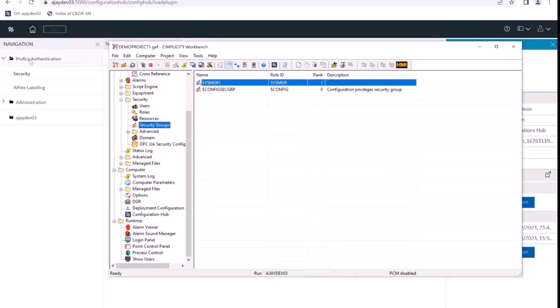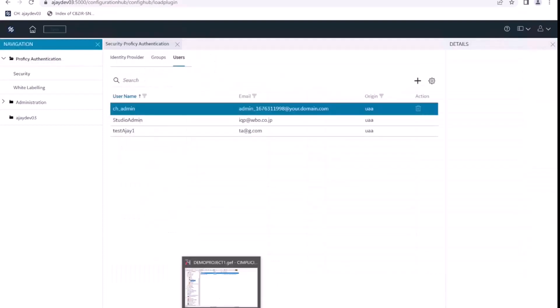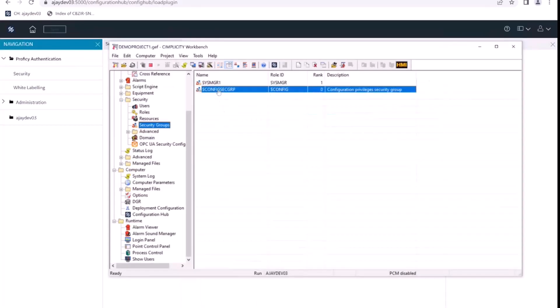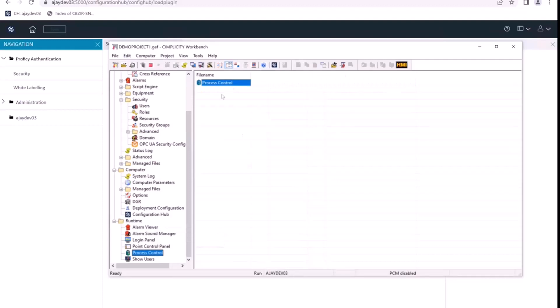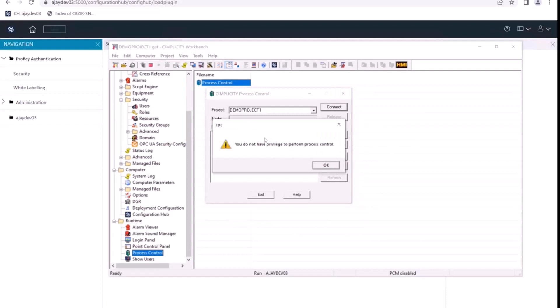Looking at Configuration Hub, we know that ch_admin has both scopes: the node-level scope, which is config sec group, and we have also assigned sysmgr1 to that user. So what rank would have priority? We gave rank one to sysmgr1, meaning that when we log in to CIMPLICITY, ch_admin would be assigned the sysmgr1 role. Logged in with the ch_admin user, and we are brought up with a window saying we do not have privilege to perform process control.